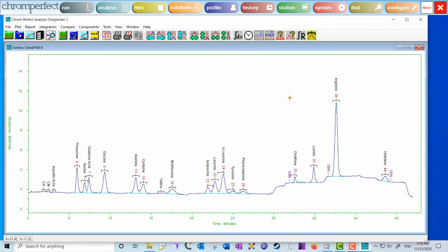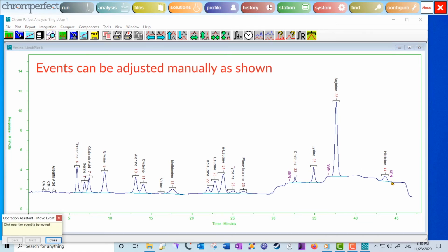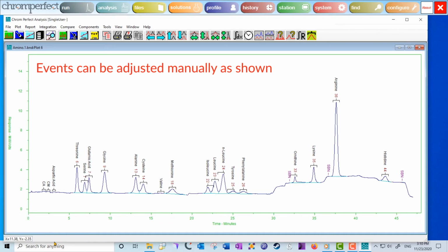The timed events will appear in the Events tab of the method, along with their retention times. These times are absolute, so be sure to place the event so that the inevitable slight peak shifts, which occur from run to run, do not cause the event to be in the wrong place relative to nearby peaks. Timed events should be monitored and adjusted as needed.